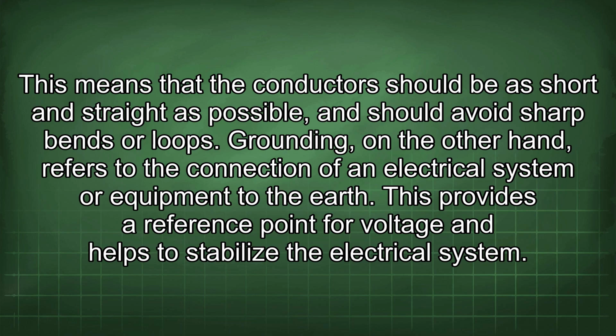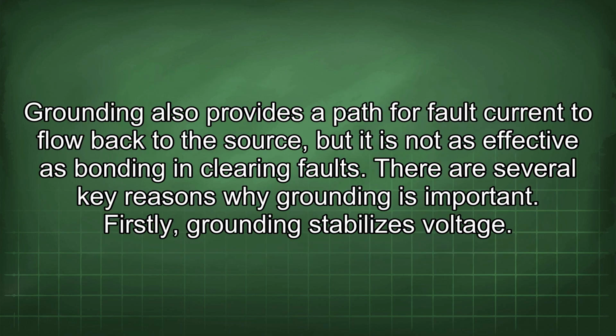Grounding, on the other hand, refers to the connection of an electrical system or equipment to the earth. This provides a reference point for voltage and helps to stabilize the electrical system. Grounding also provides a path for fault current to flow back to the source, but it is not as effective as bonding in clearing faults. There are several key reasons why grounding is important. Firstly, grounding stabilizes voltage.